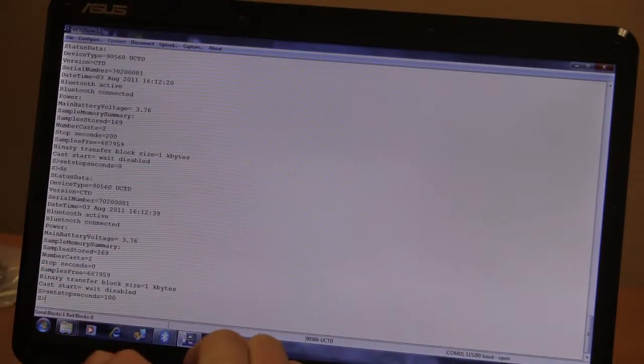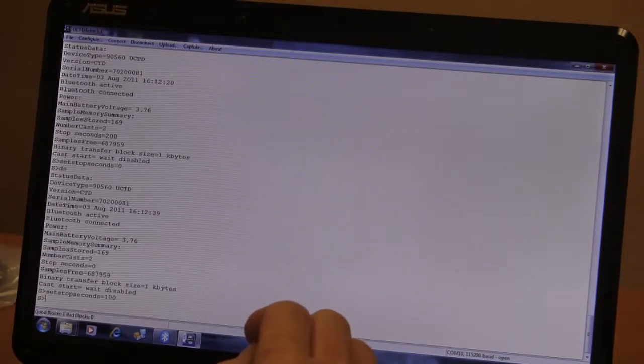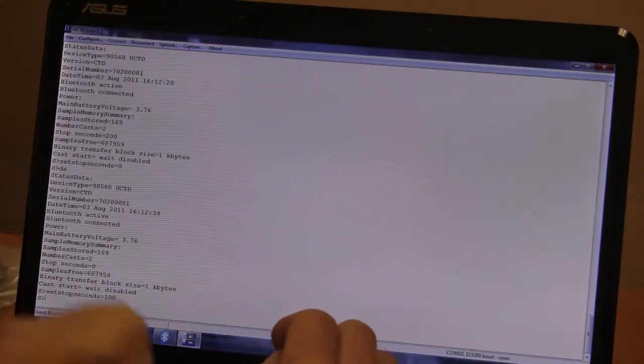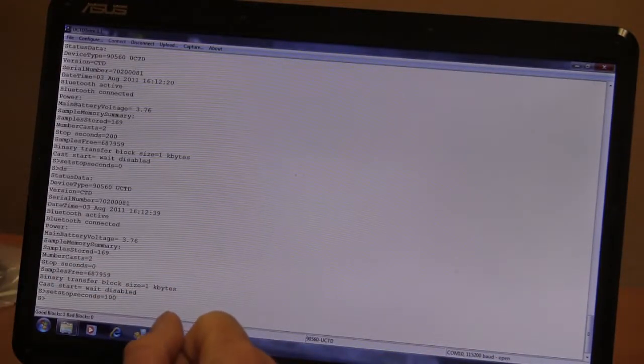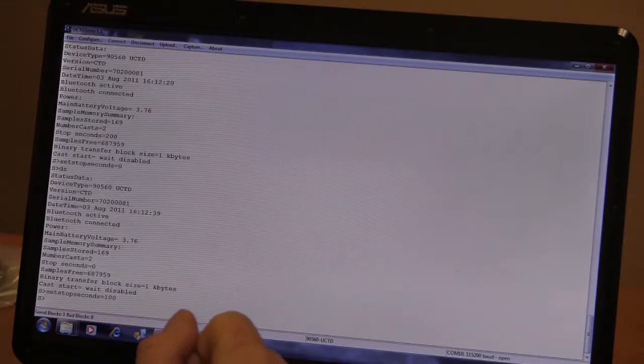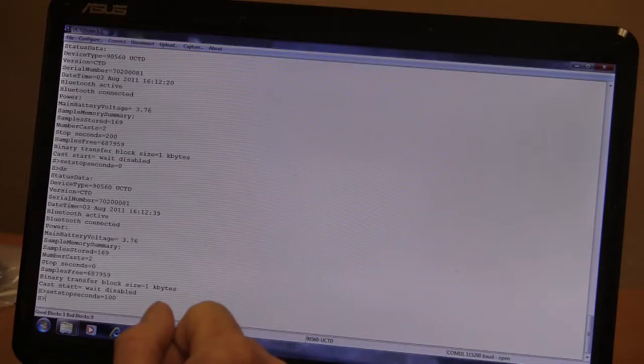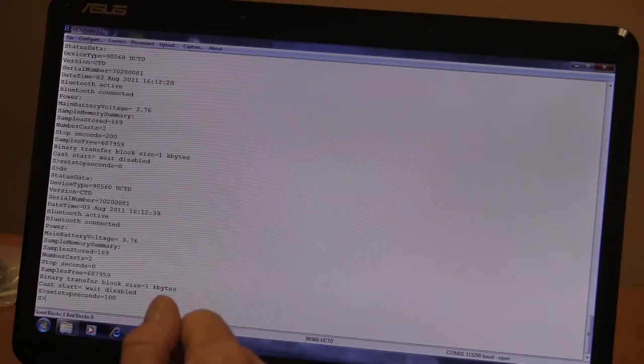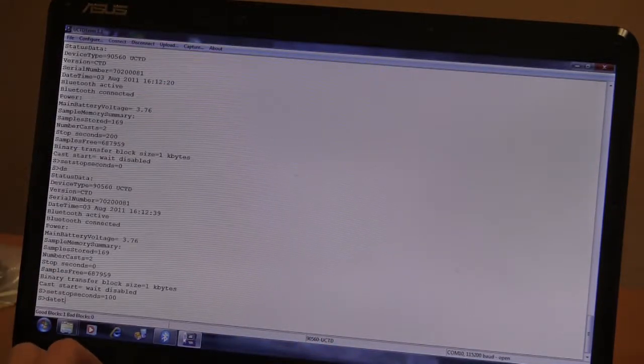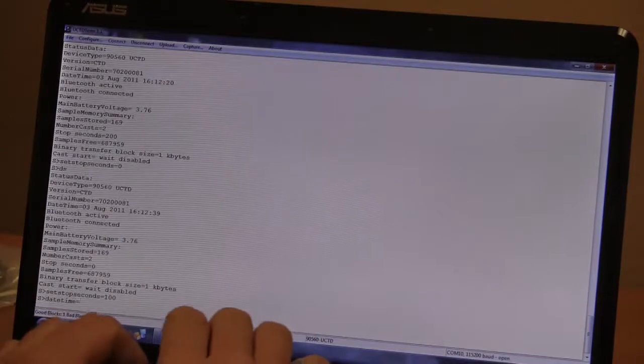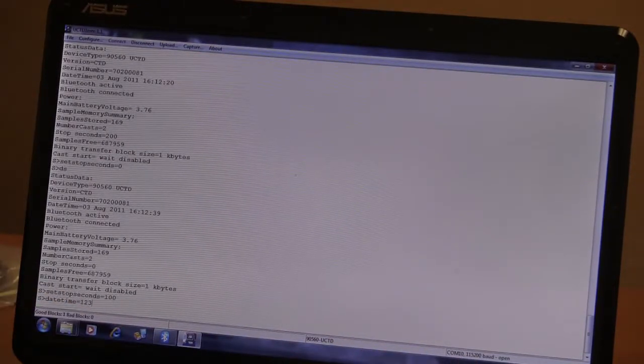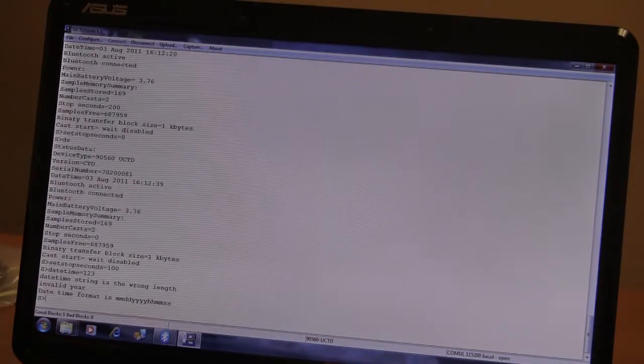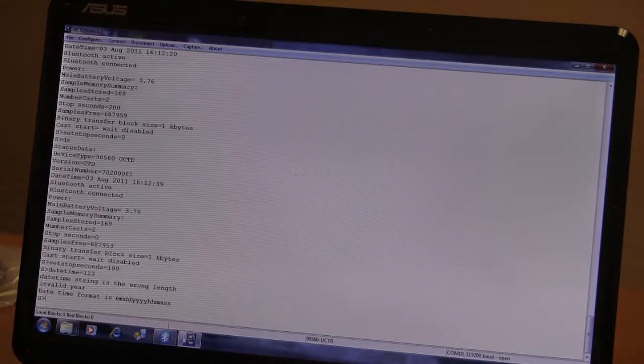Now if we want to synchronize the probe clock with the GPS clock, you have to set the clock on the probe to whatever time zone you use. In this case, typically it's Greenwich Mean Time to synchronize with a GPS. The way you do it is date time equals, and since I can never remember the syntax of that command, I just press one, two, three, and it's going to complain that I entered the wrong format. But now it actually gives you information about what the correct format should be.